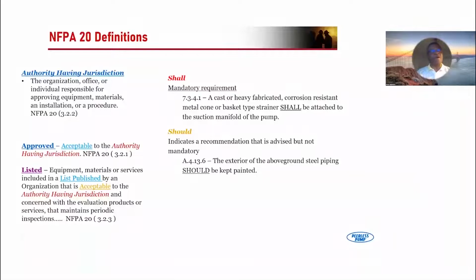When we talk about a fire pump being approved, that means it is acceptable to the authority having jurisdiction, which I'll refer to as AHJ for the rest of the presentation. Any listed equipment is equipment or fire pumps that have been independently looked at and tested by an organization, like UL or FM, published on a website, and also acceptable to the authority having jurisdiction.